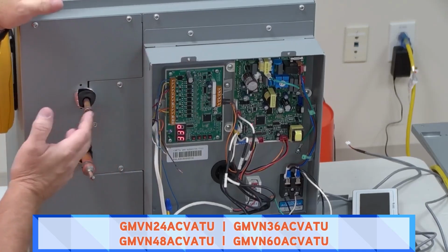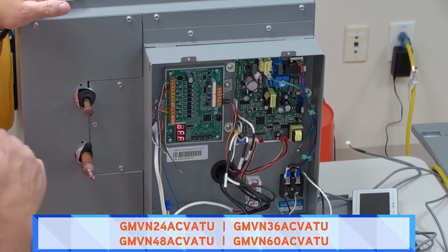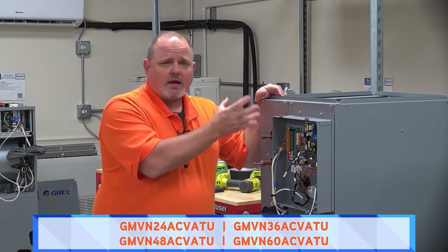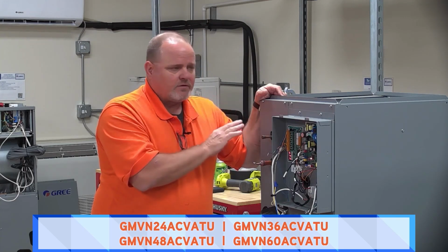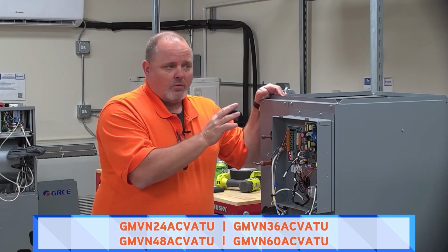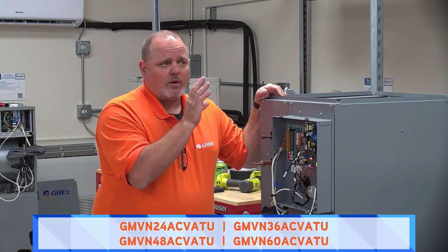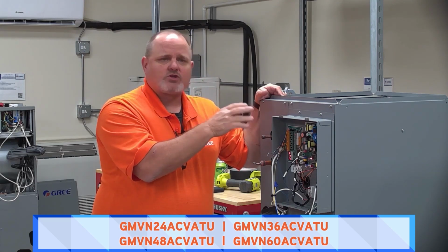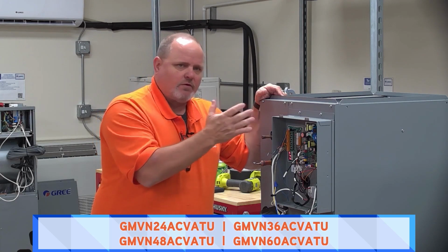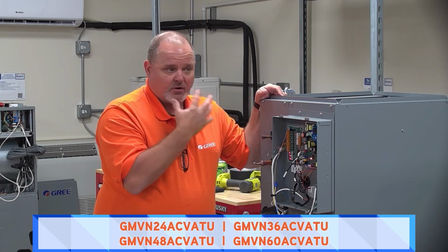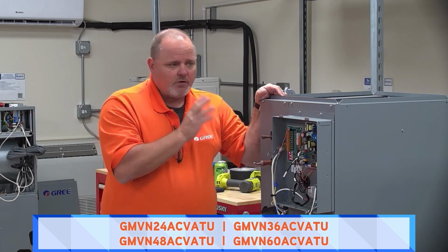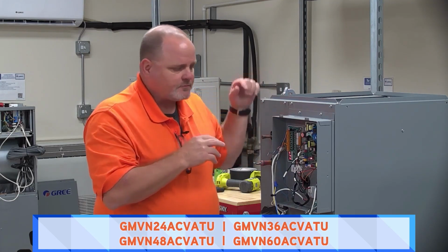It's also already set up to do 24-volt control and to tie in with the communicating MultiPRO unit. Before we get into all the controls, I thought we'd talk a minute about the coil we have opened up here, what's featured inside the coil, and what you're unplugging if you move the control box, or even if you don't. So let's move over to this larger coil.